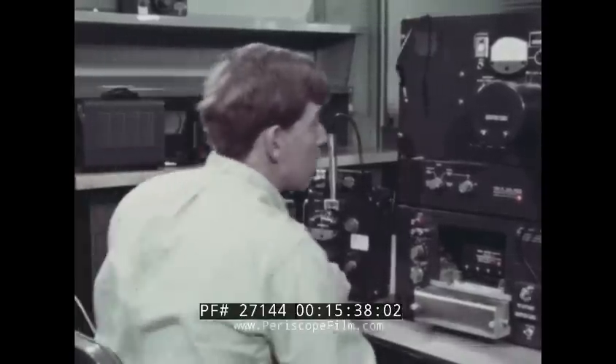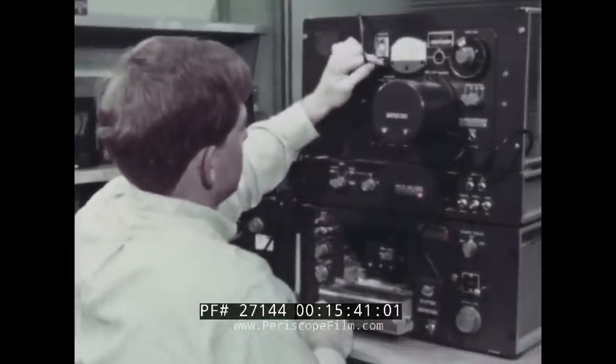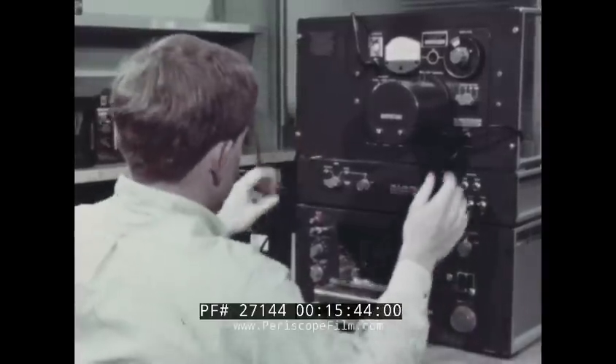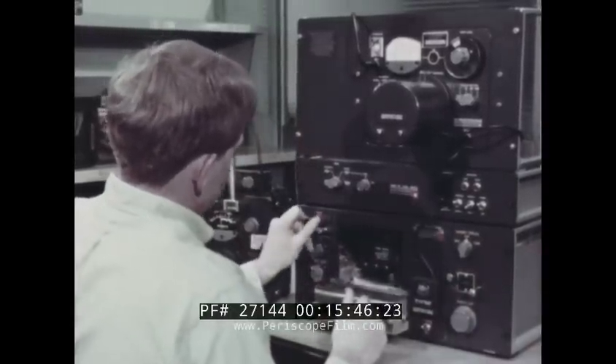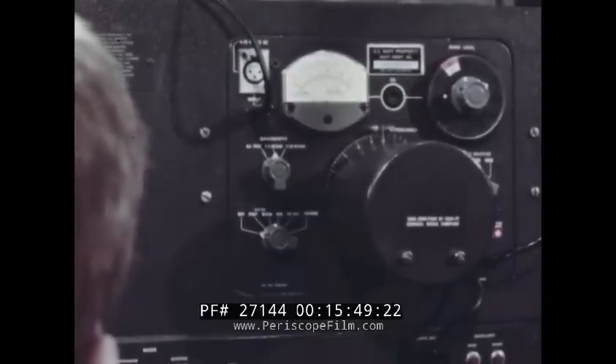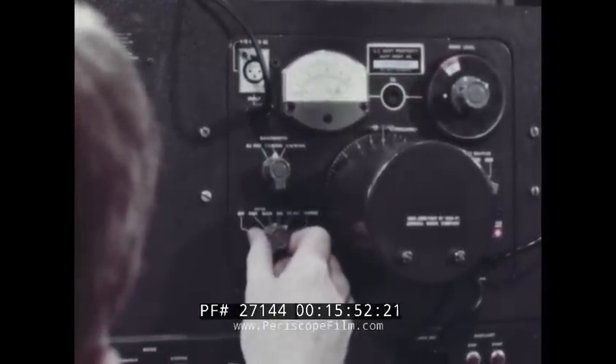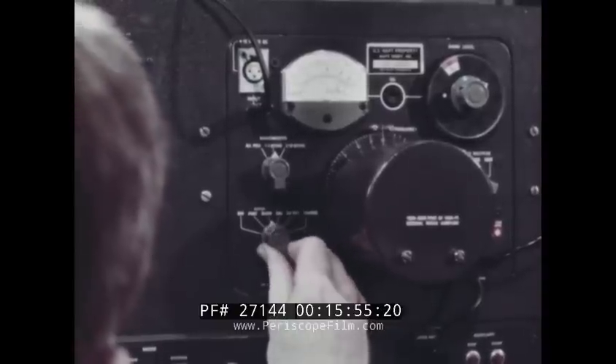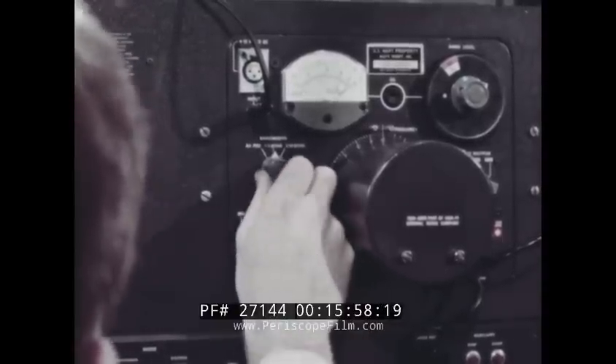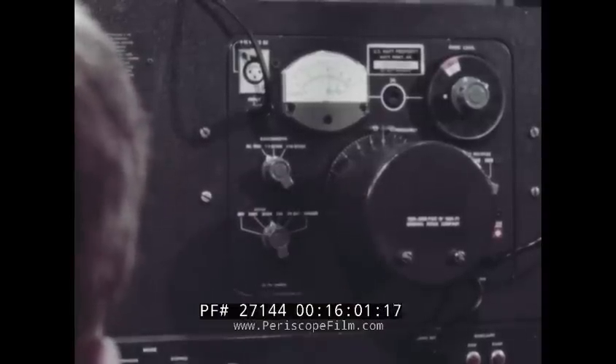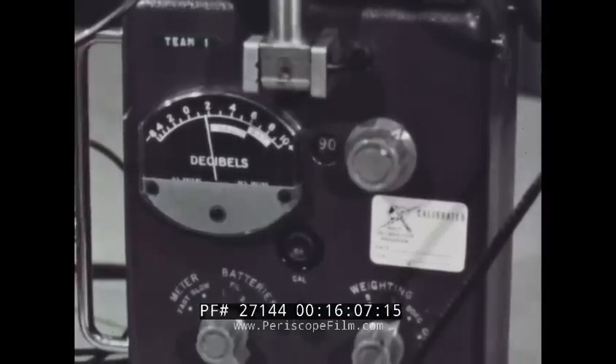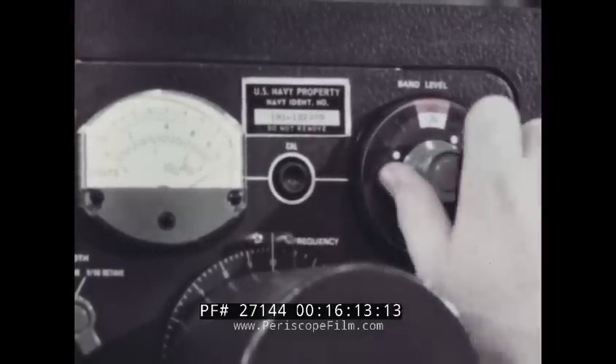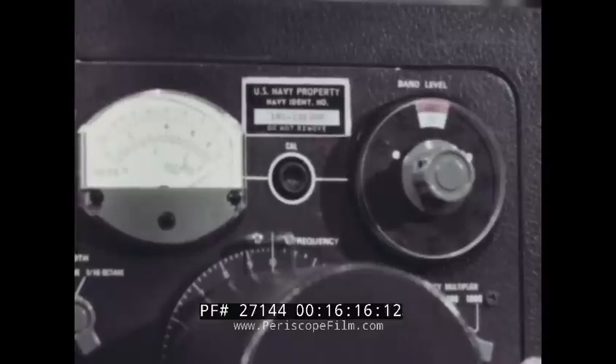After you've calibrated the sound level meter, connect it to the analyzer. And connect the analyzer to the graphic level recorder. Now, calibrate the analyzer so its reading matches the reading of the sound level meter. To do this, set the analyzer to measure broadband noise by putting the selector switch on all pass. On this type of instrument, there are two controls for meter range. Set the inner dial and the outer one to provide an on-scale meter reading.